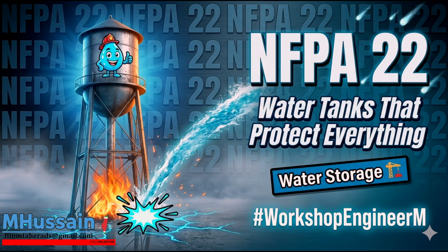You are trading physical space, specifying a massive steel vessel that eats up mechanical room square footage, in order to lower the required operating pressure to safe levels. That is the fundamental engineering compromise, trading spatial footprint for pressure reduction. And regarding those massive steel vessels, the manufacturing and testing requirements are incredibly intense. The standard requires they be hydrostatically tested to at least 150 psi.